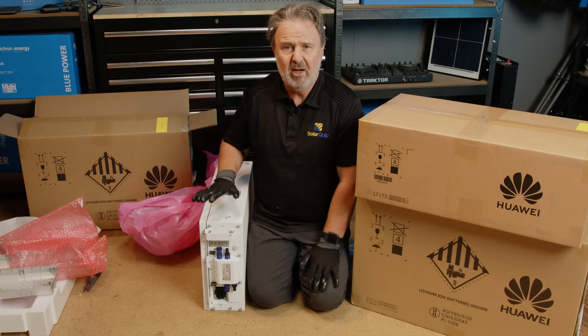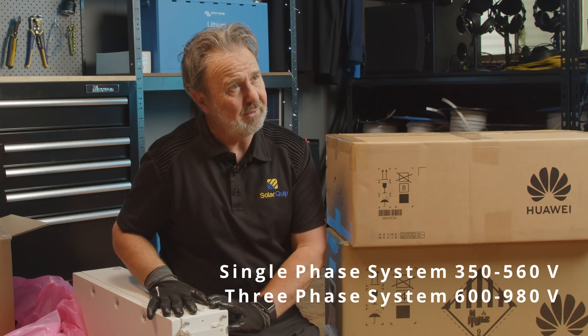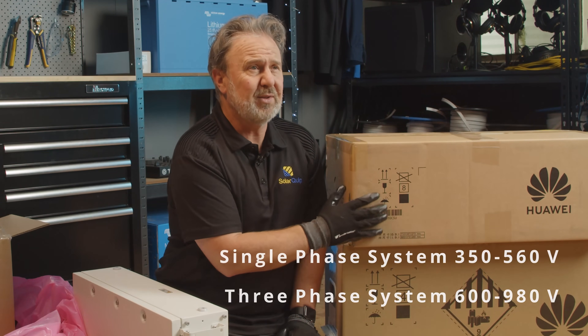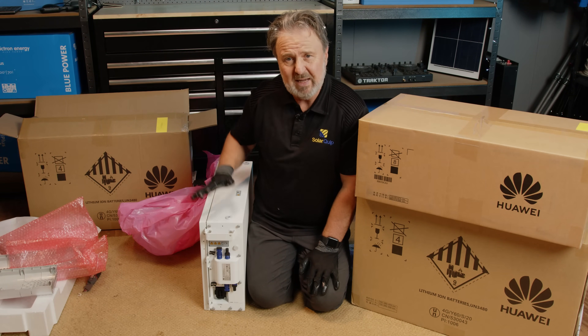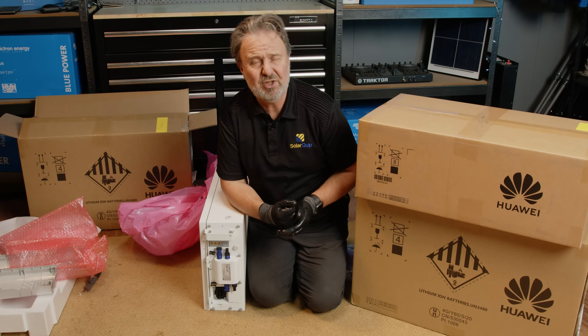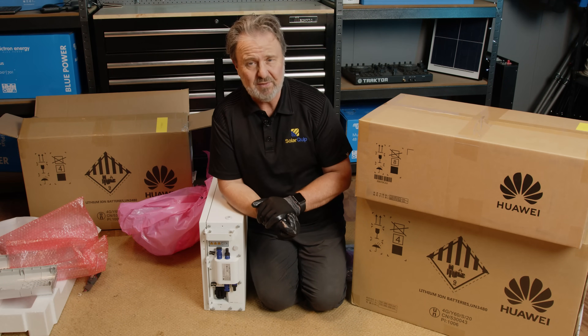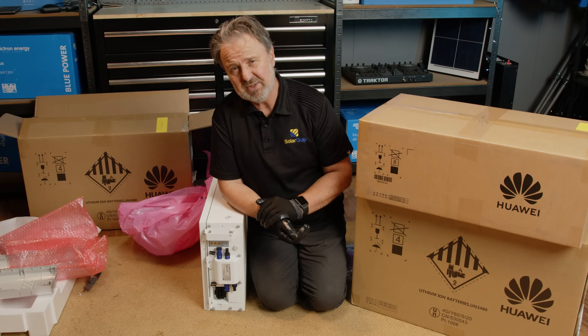This is one of the advantages of what Huawei has done — avoid that by paralleling their battery modules. These battery modules operate up around the 400 volt mark each, and they are paralleled. The controller is basically a DC-DC converter, and when you add another battery module it's still the same voltage output because they're in parallel. The BMS manages them independently, so it can discharge one battery module and not another — it can cycle them progressively and balance them precisely. That's one of the big pluses of this parallel battery module design.